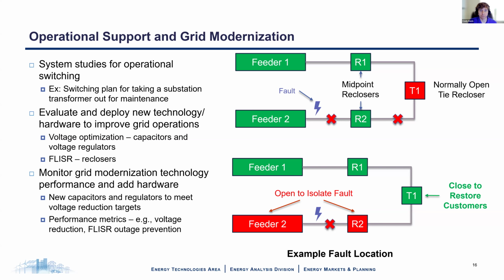The other thing is to help evaluate and deploy new technologies and new hardware to improve grid operations. So I mentioned voltage optimization and FLISR earlier on. On the right here, we have an example of how FLISR actually operates. So we've got two feeders, feeder one on the top, feeder two on the bottom. The top set of feeder one and feeder two is the before, and the bottom part is the after. So we're going to introduce a fault just outside of the exit of feeder two, and that's going to de-energize all of those sections with the red X's between feeder two and that T1 normally open tie recloser. Well, I've got these two other reclosers here, R1 and R2, that I'm calling midpoint reclosers.